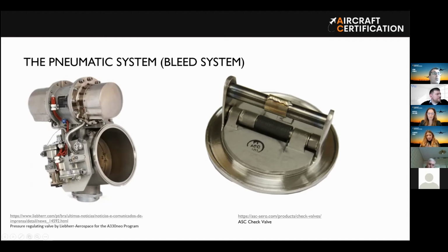So the torque motor will receive the analog signal from the AMS controller, and with this analog signal the piston will be controlled and will provide modulation for the butterfly here. Here you have a typical bleed check valve. It's a two flapper check valve, as you can see.